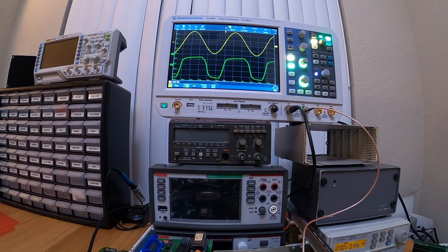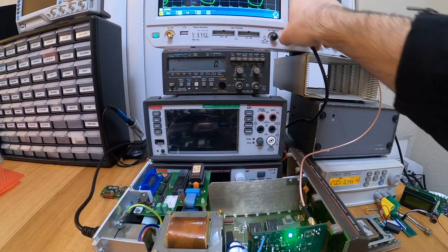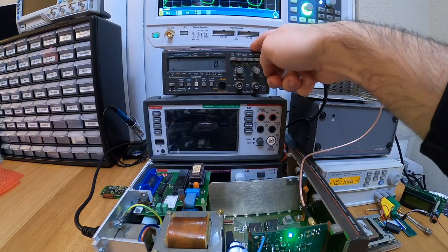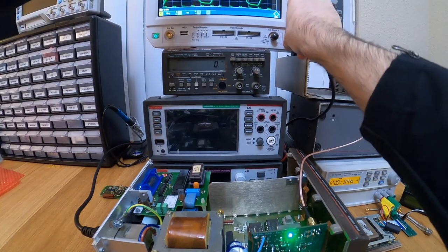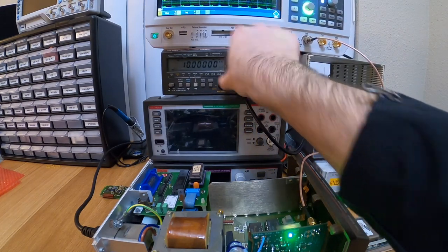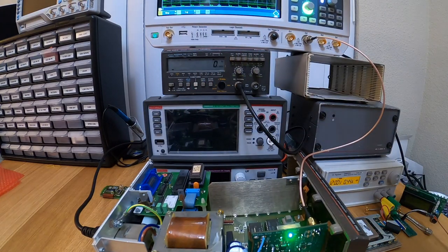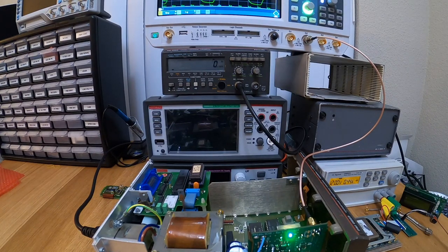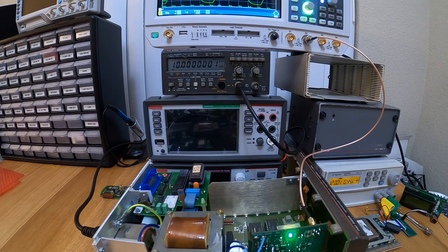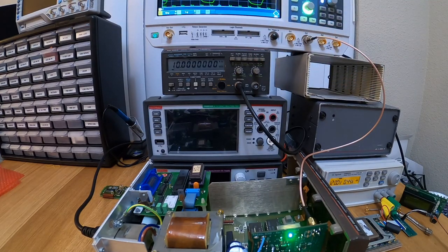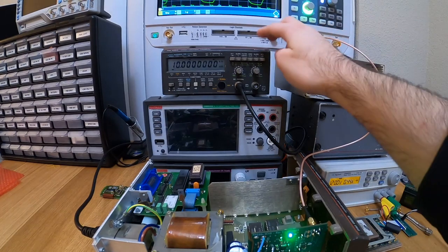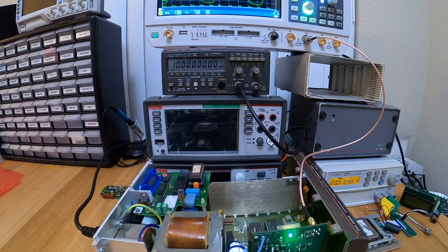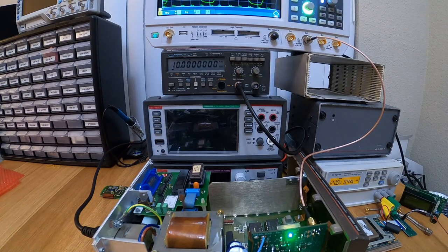Definitely not moving. And also a quick check to see if it's actually very stable is to take my 10 MHz reference, which I used to calibrate the OCXO in that counter a few weeks or even actually maybe one month or so ago, and I can do a reading again. Move to a 10 second measurement time. And let's wait a bit more because the first reading is expected to be a bit off because I connected it and there could be some problems because of that. And dead on, 10 MHz, dead on, nothing more, nothing less. So the OCXO inside here is aging pretty well. It's possible there is a slight difference, but it's below the reading precision or the resolution of the display here. So it's a non-issue.